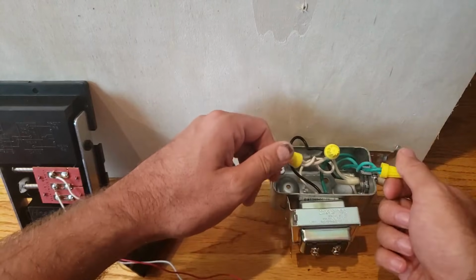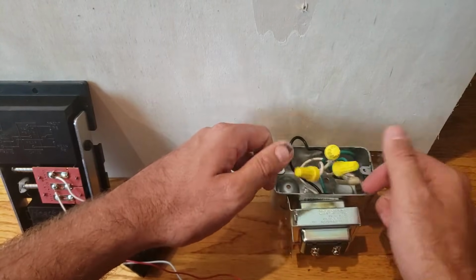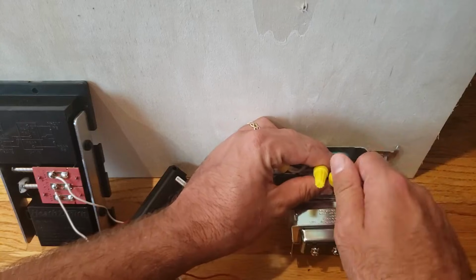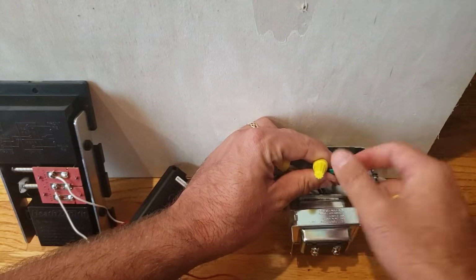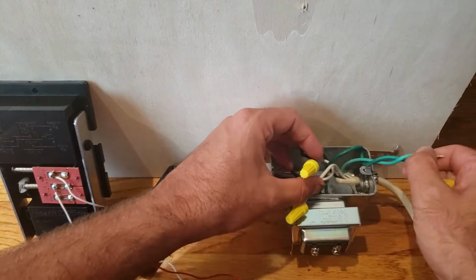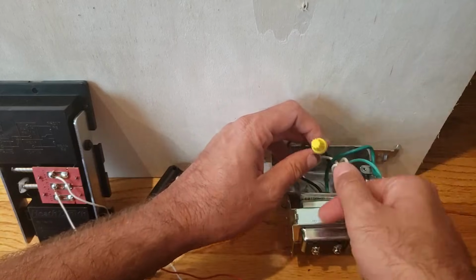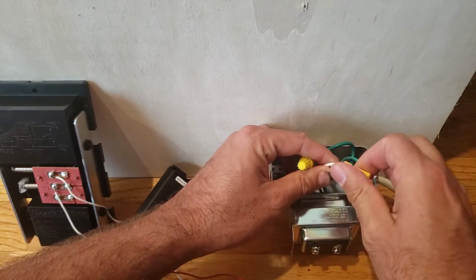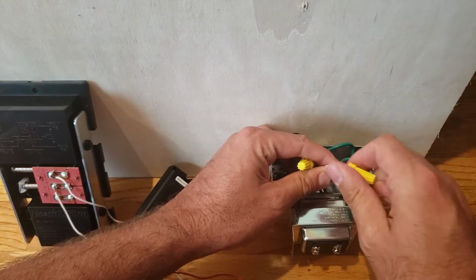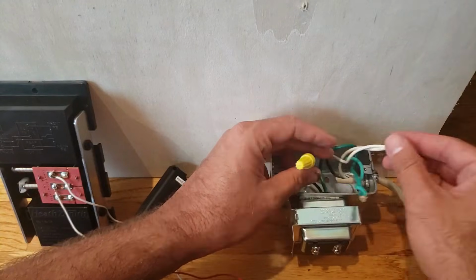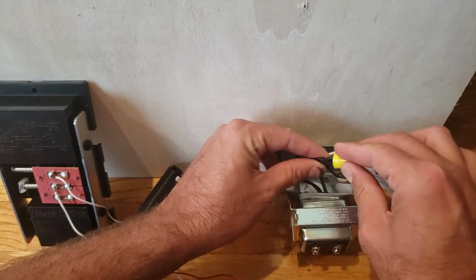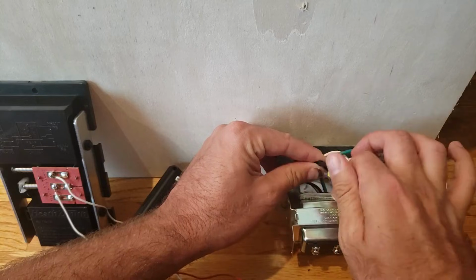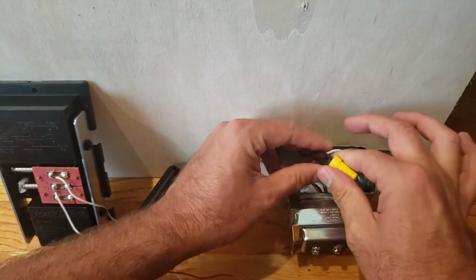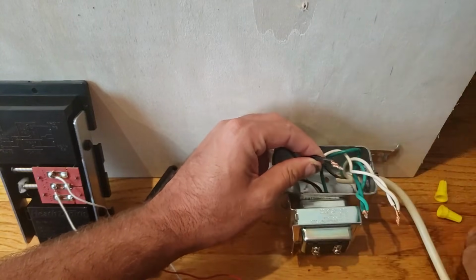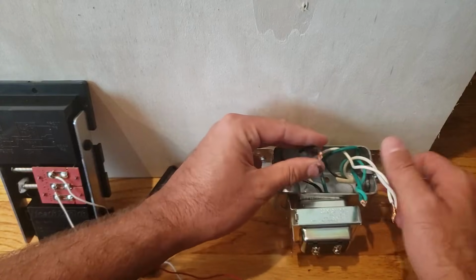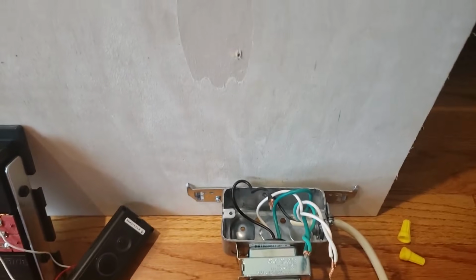So what we're going to do first is remove all these wire nuts. You may have more wires in there, but you should have the same color wires: green, white, and black. In some locations you'll have a different colored wire like red, and that colored wire is going to be your hot wire, or the circuit wire. White is always neutral, and green is always ground. Those are universal color codes for electrical wiring.